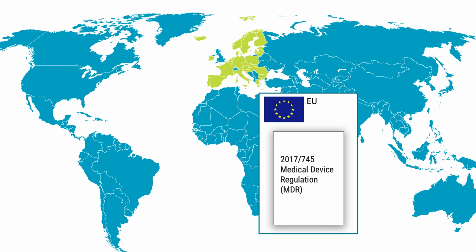Remember, it's mandatory for all manufacturers to have a PRRC available if you are CE marking medical devices according to the MDR. The PRRC requirements also apply to any European representative for those manufacturers needing that, meaning if you are a manufacturer from outside the European Union, you need to have your own appointed PRRC.